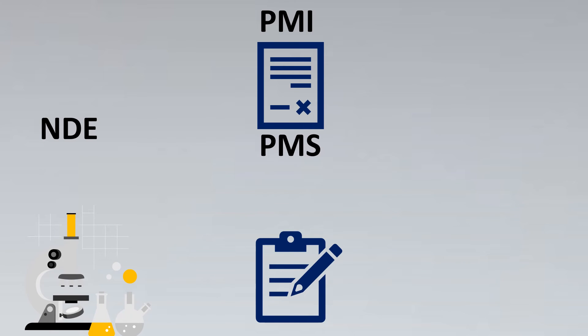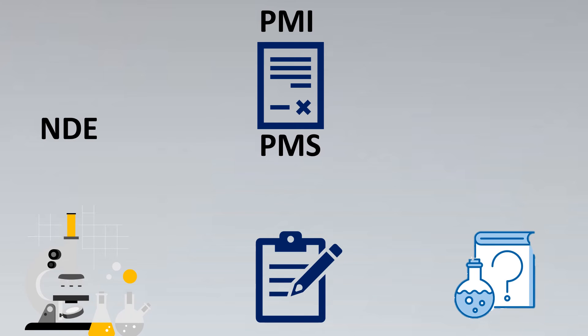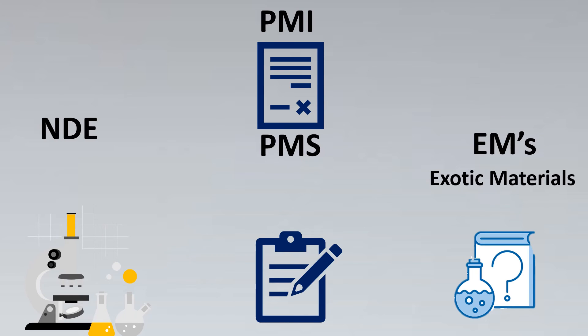As a thumb rule, you can also use PMI when your service is too corrosive, too toxic, or has special requirements and needs exotic materials. When you need such materials — like Hastelloy or stainless steel and other exotic alloys — clients usually go with PMI for identification so that they are sure that the material they specified is what the vendor has delivered.